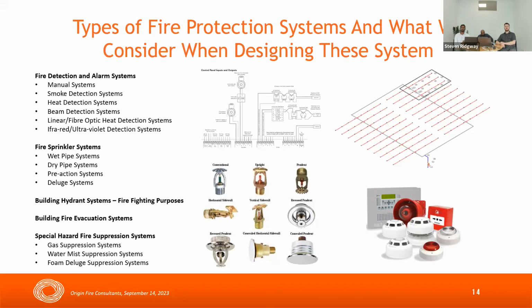Fire detection systems can consist of manual alarm systems, smoke detectors, which are typically optical smoke detectors, heat detectors, beam detection, linear and fiber optic heat detectors, and infrared ultraviolet detection systems. As an example, linear fiber optic heat detection systems are commonly used in tunnels, and infrared ultraviolet detection systems, which are basically detectors looking for the radiation emitted from a fire, are commonly used in aircraft hangars. And where required, smoke detectors and heat detectors are located throughout the building.